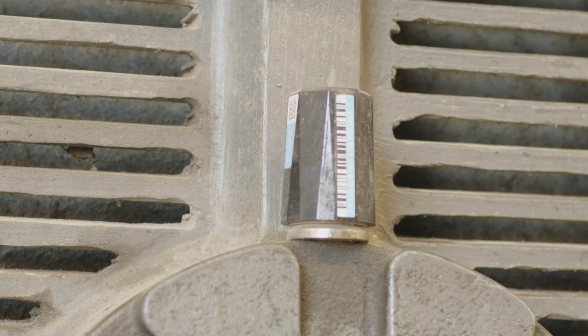Now, when it comes to the monitoring itself, these are remote sensors, right? Yes. You don't have to go out there and check on them. I'm sure you do general inspections on the equipment, but are they staying put well? They are. They have a magnetic base. It's actually glued to the unit itself, so they stick very well, and we've never had an issue with them coming off. We've had one failure, but that was a battery failure, an internal component. AssetWatch was very good about sending us new ones as part of our contract.